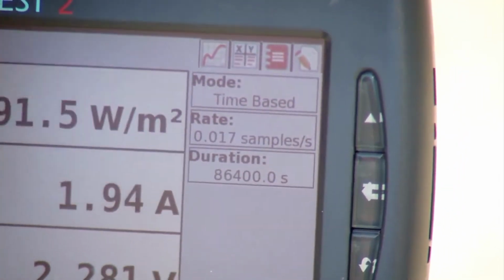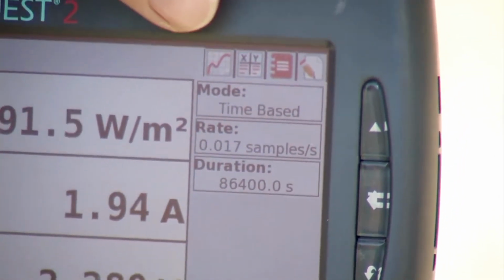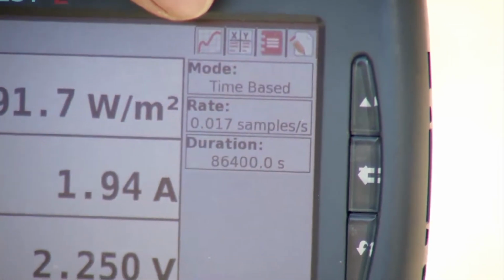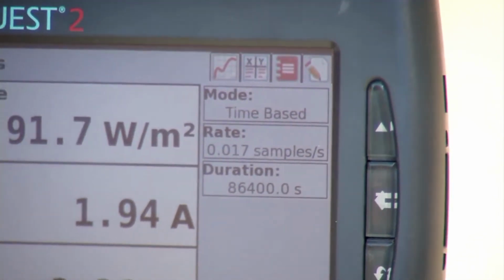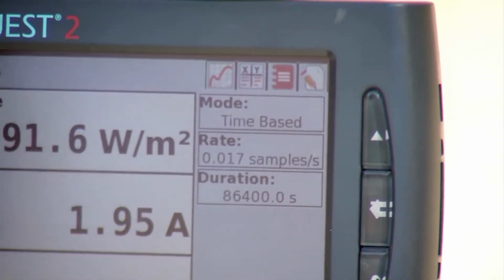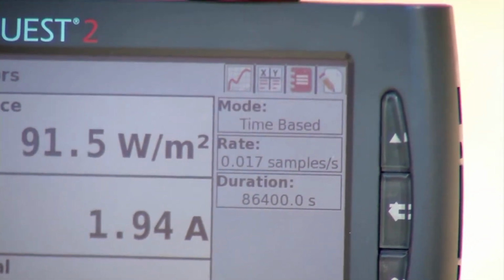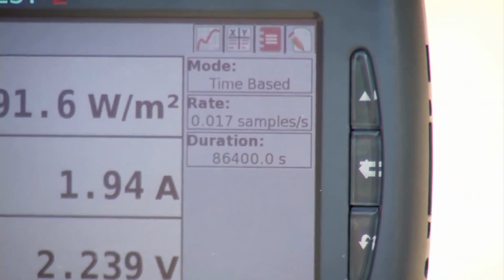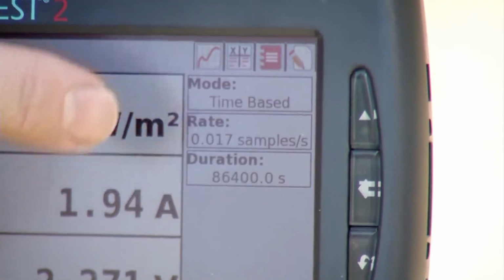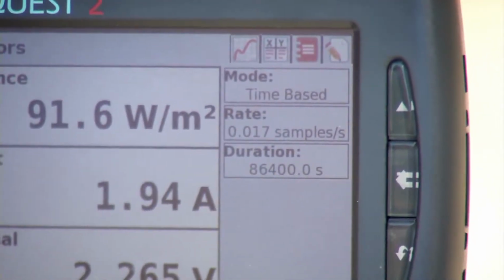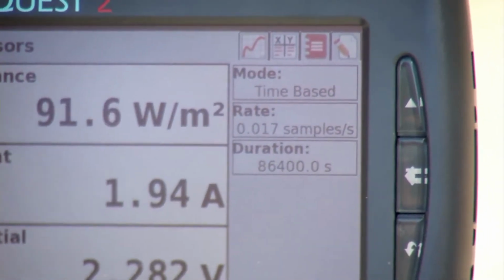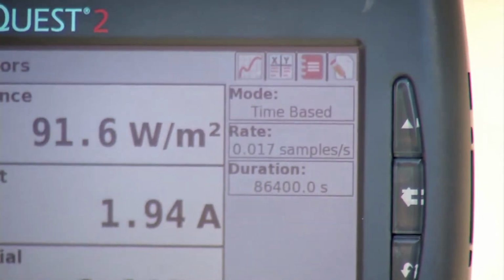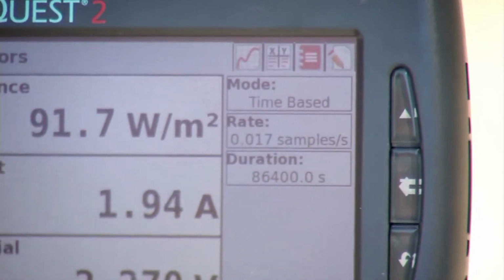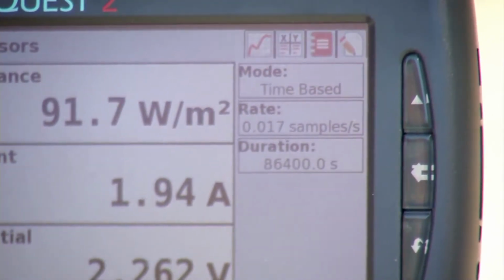Now that we've set the screen to high contrast, and we see our 3 sensors there, we might want to take a look at our default collection parameters. Its mode is time-based, so it's going to be looking at these different variables as a function of time. The sample rate is 0.017 samples per second. That's actually once every minute, and the duration is 86,400 seconds. That's actually a 24-hour collection, so it's designed to track solar radiation throughout an entire 24-hour period.